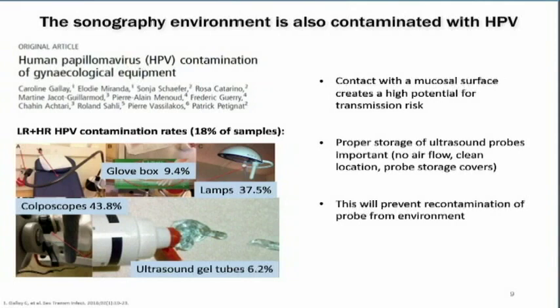So contact with mucosal surface creates a high potential for transmission risk. Proper storage of the ultrasound probes is important, that there's no airflow, that it's in a clean location, and that the probe storage has a cover. This will prevent recontamination of the probe from the environment.